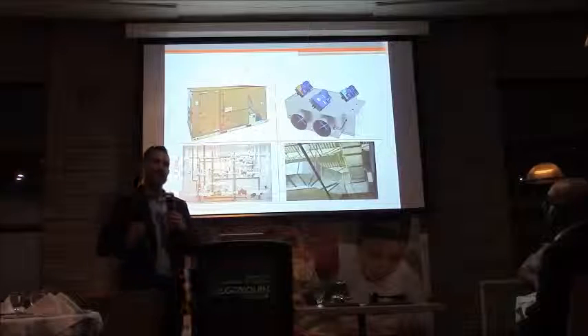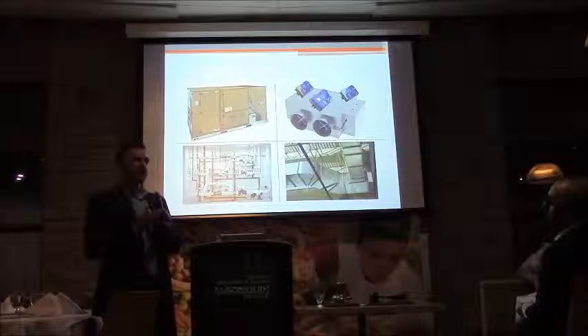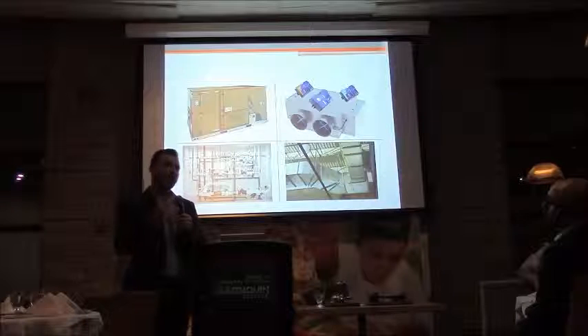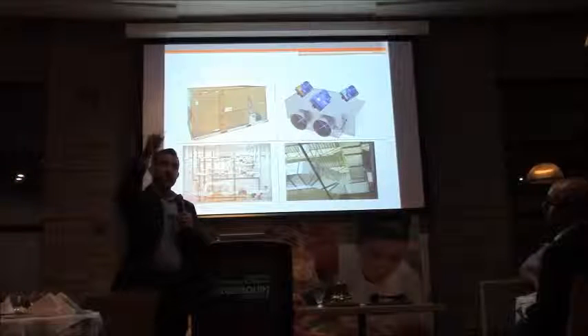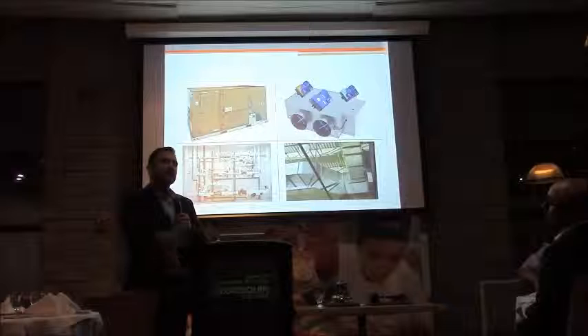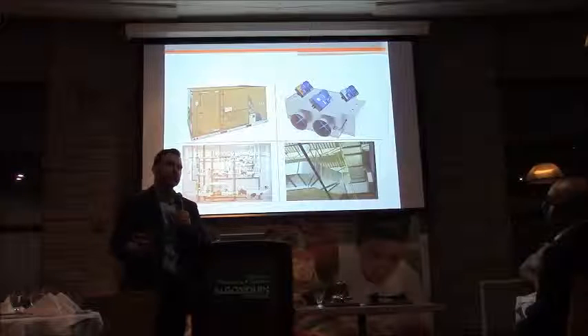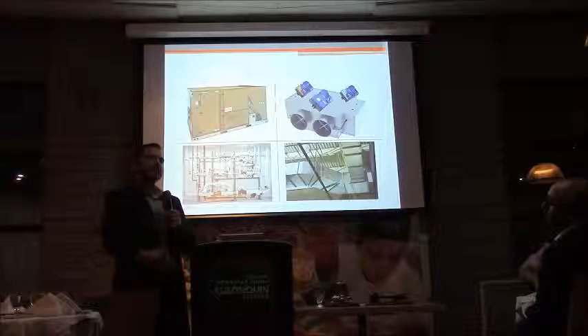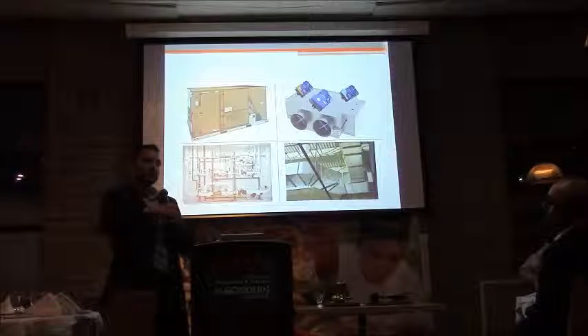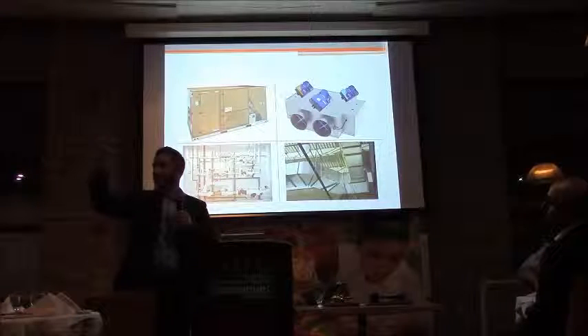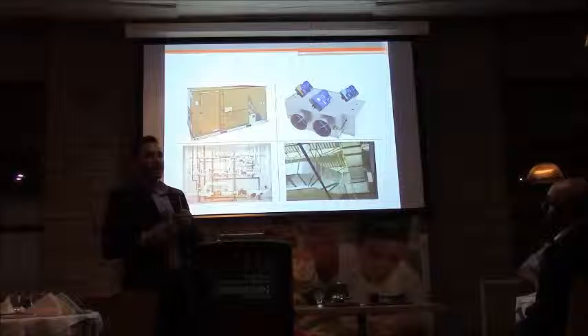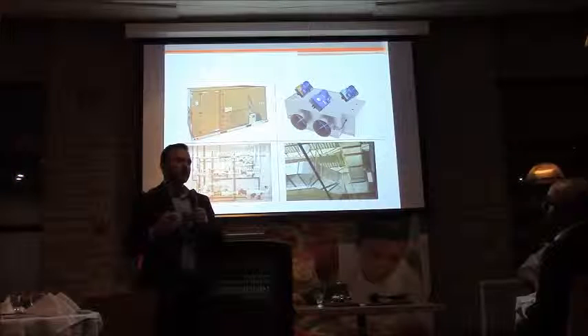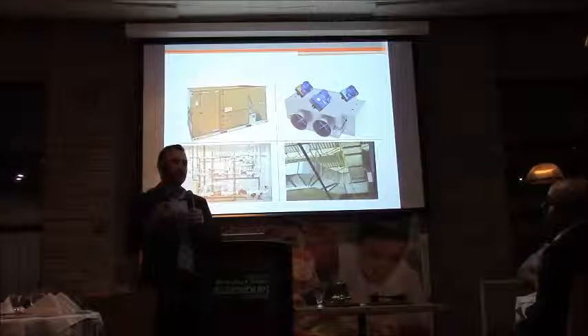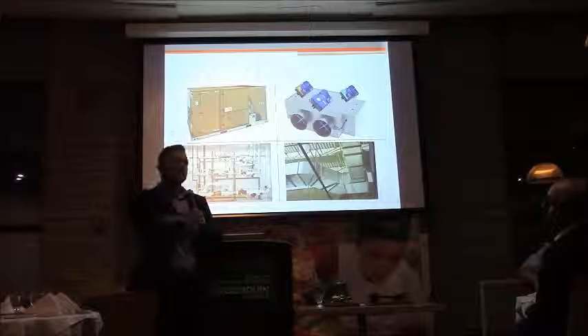The reason being is that once you reach minimum, if you don't have enough CFM coming out of your diffuser, the airflow is just going to start dropping down vertically. It's called a cold air shower. It's going to start dropping vertically on the people sitting under the diffuser. So anybody sitting under a diffuser while we're modulating down the airflow is going to get high velocities of cold air showering on their body.